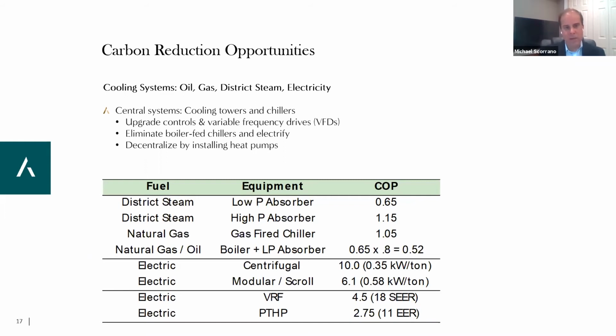You can see that district steam with a low pressure absorber, or single effect absorber, has a very crummy coefficient of performance, so we have to put a lot more energy in to get energy out. Then we can look at district steam with higher pressure, which has a little better efficiency, and the same thing with natural gas and with boilers. But those technologies are very limited in terms of coefficient of performance.